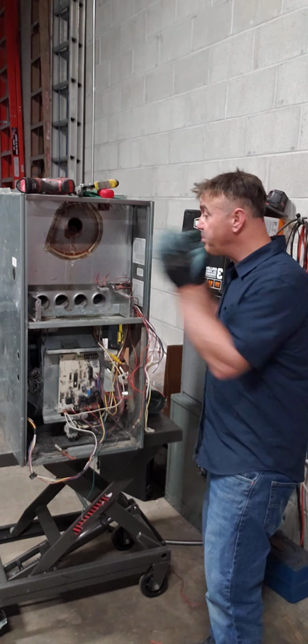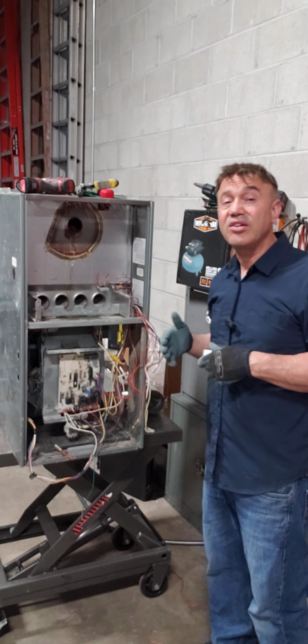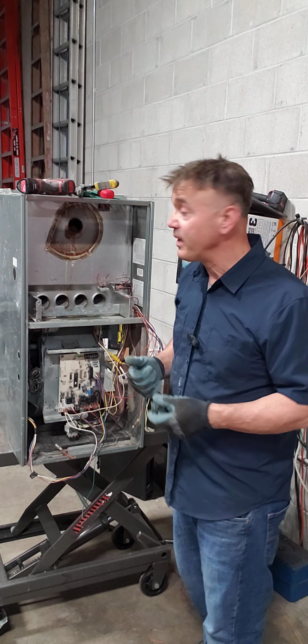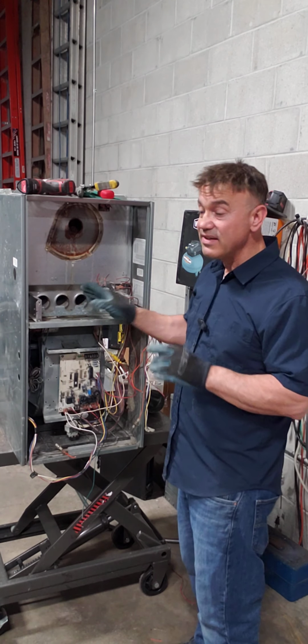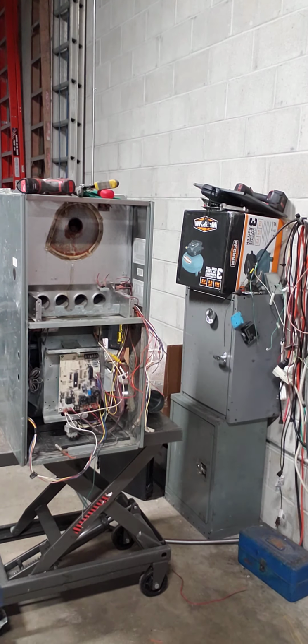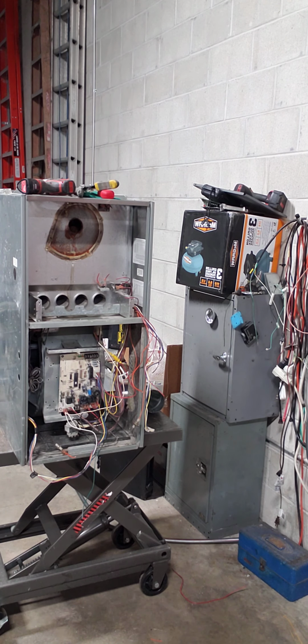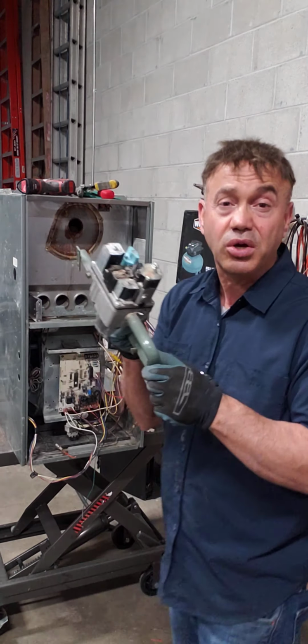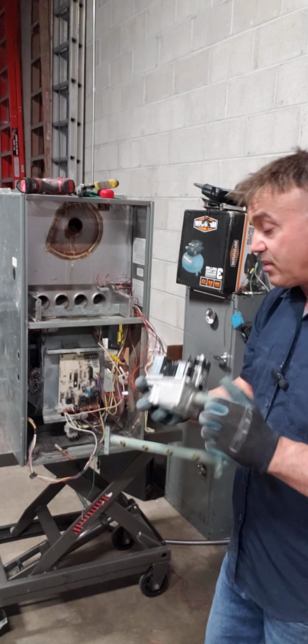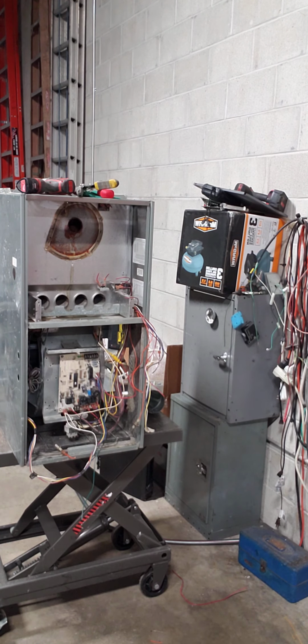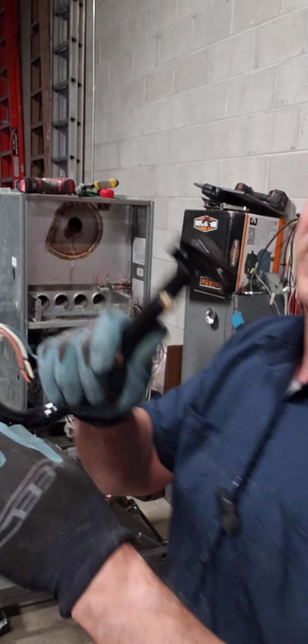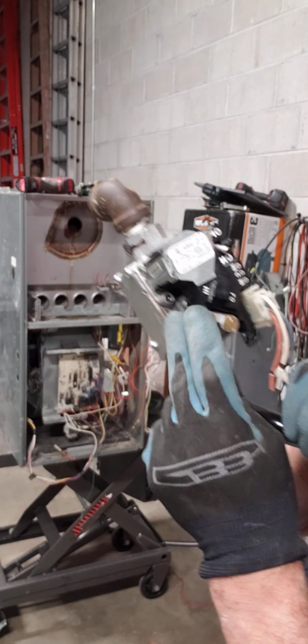So the installers come and put in the furnace, but they have to send a startup team or startup guy. Usually they make sure the gas valve isn't pushing the gas too crazy into the furnace. There are some adjustments - some units don't have adjustment, unfortunately, but this one, like Carrier, has adjustment. You can remove this; it's 2-stage, but you have to know how to do it.